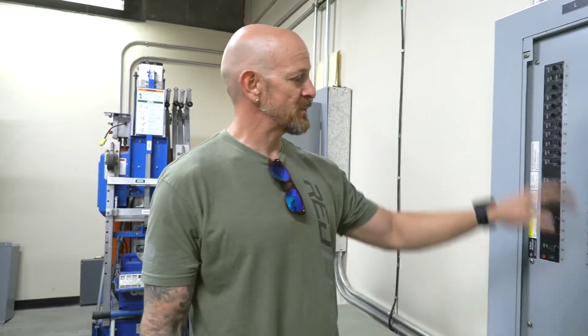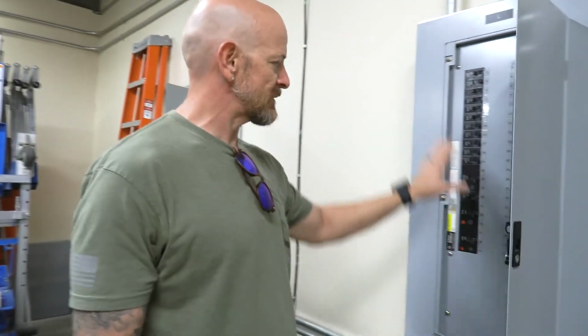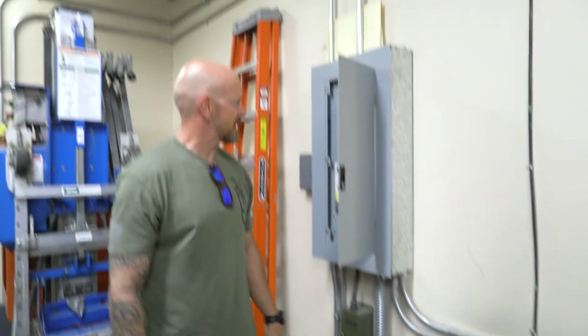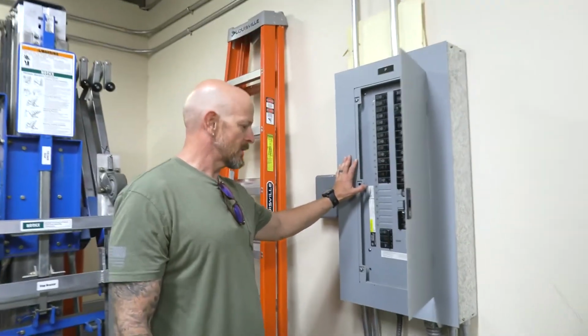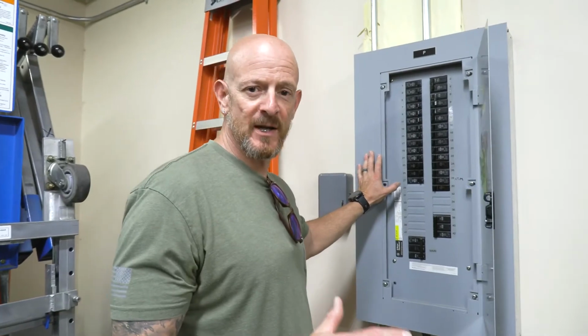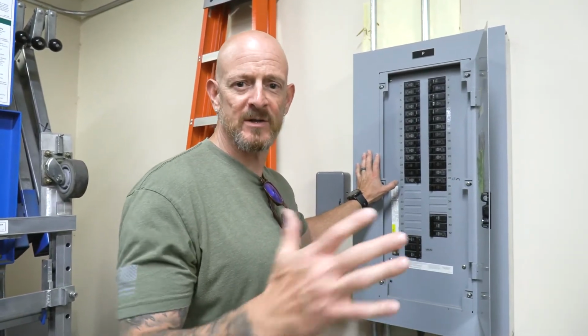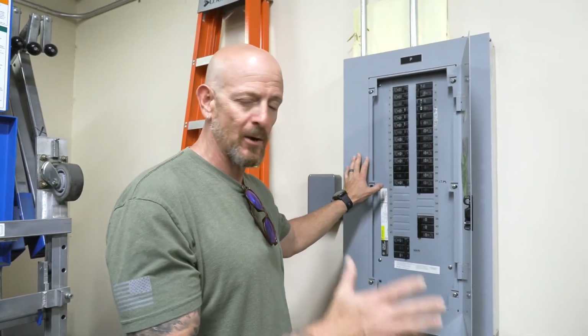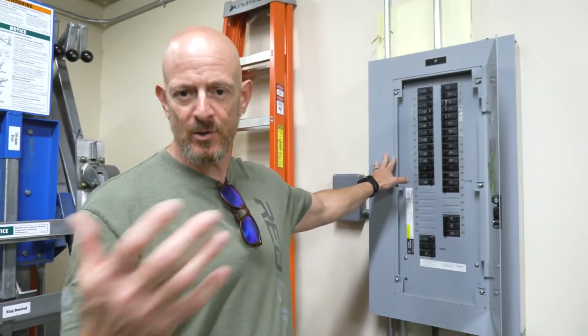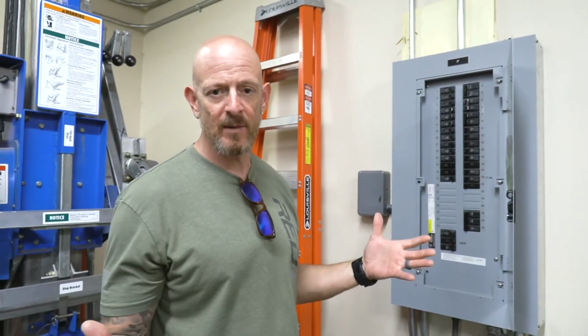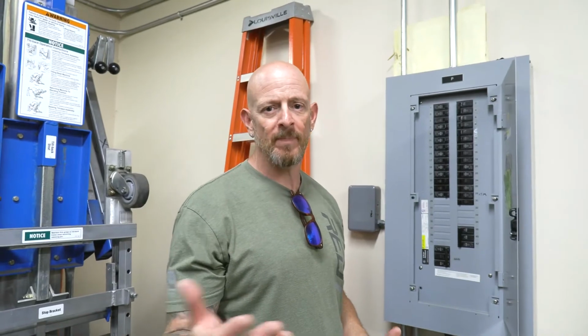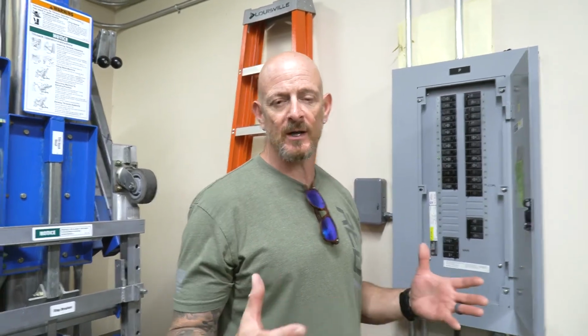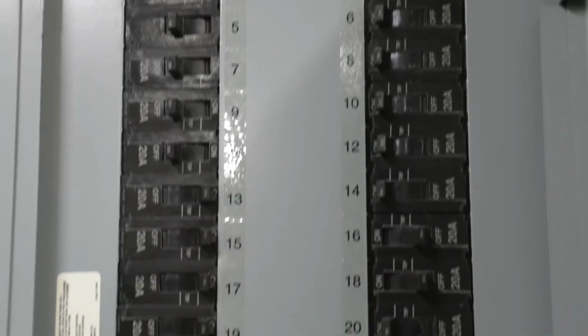This high voltage panel, it's a 480 volt, a 277/480 volt three-phase. This also feeds into this transformer here. It's a 30 kVA transformer, which feeds a low voltage. So you see that typically in a commercial setting where a lot of buildings have 480 volt, 277/480 volt, and then you have to transform that power down to 120/208, which is the normal stuff that we use on an everyday basis. 120/208 three-phase is typically something you see in a commercial setting. 120/240 single-phase is something you see in a residential setting.